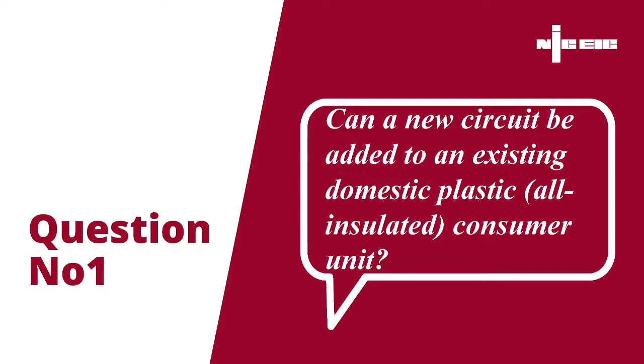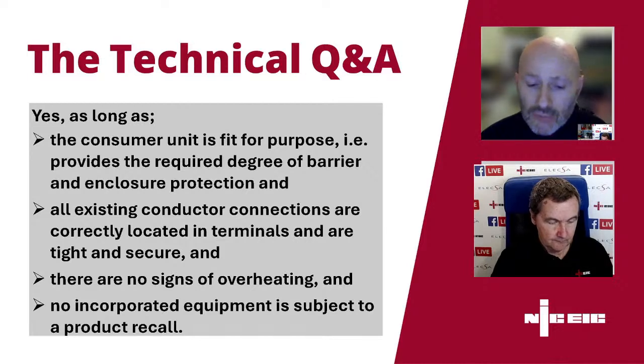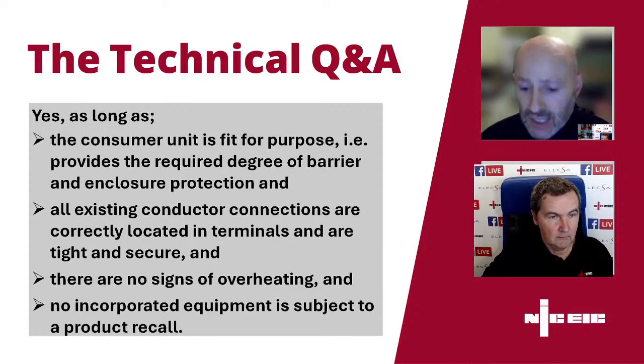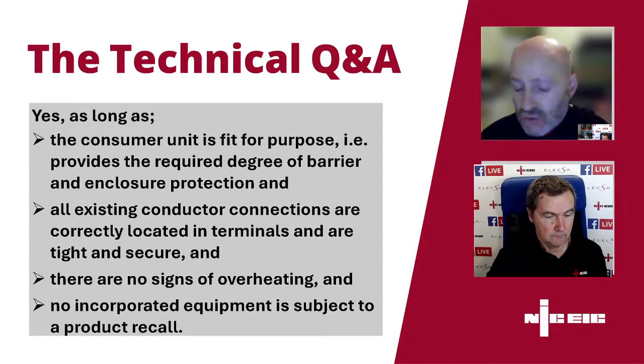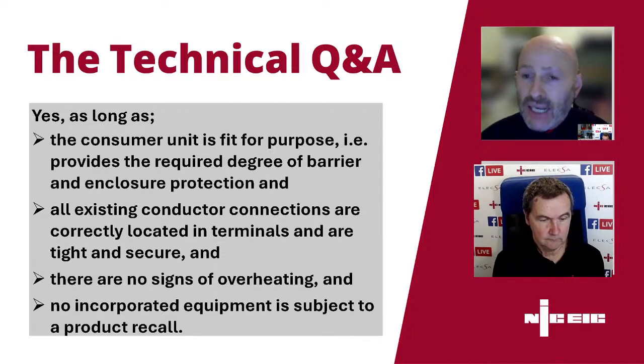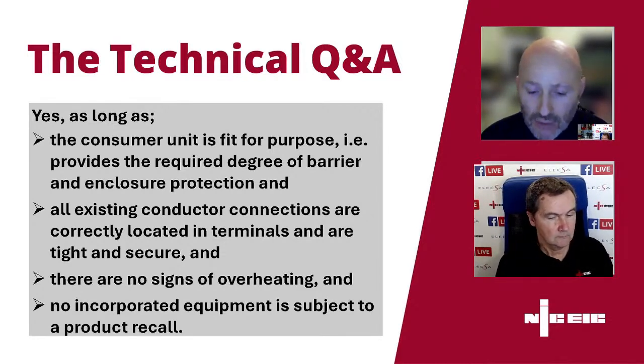So before I answer the question, I'm just going to say this topic comes up a lot during our assessments. I imagine it's not just me as an assessor alone in the area I cover, but this comes up a lot. The answer is yes. There's obviously criteria to meet to ensure that, some of which I'm going to go through now. The consumer unit still needs to be fit for purpose. Obviously still provides the appropriate degree of barrier and enclosure protection. That's the first one. All the existing conductor connections are correctly located in their terminals and are tight and secure as per manufacturer's instructions. Obviously no signs of overheating in and around the consumer unit itself.